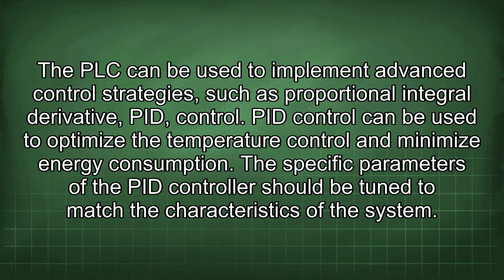The PLC can be used to implement advanced control strategies such as proportional integral derivative (PID) control. PID control can be used to optimize the temperature control and minimize energy consumption. The specific parameters of the PID controller should be tuned to match the characteristics of the system.